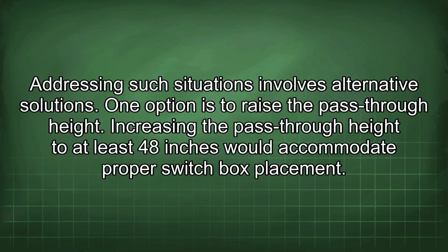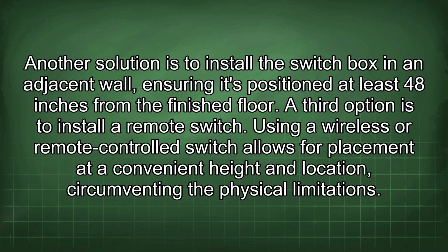One option is to raise the pass-through height. Increasing the pass-through height to at least 48 inches would accommodate proper switchbox placement. Another solution is to install the switchbox in an adjacent wall, ensuring it's positioned at least 48 inches from the finished floor. A third option is to install a remote switch. Using a wireless or remote-controlled switch allows for placement at a convenient height and location, circumventing the physical limitations.